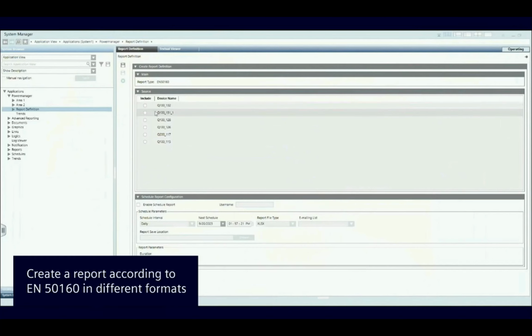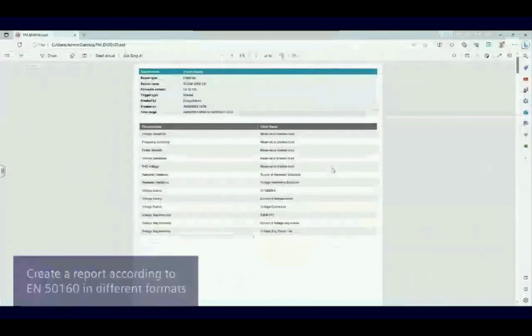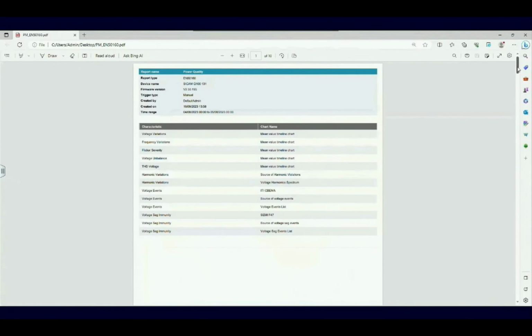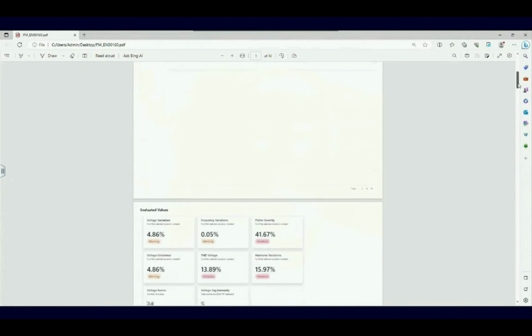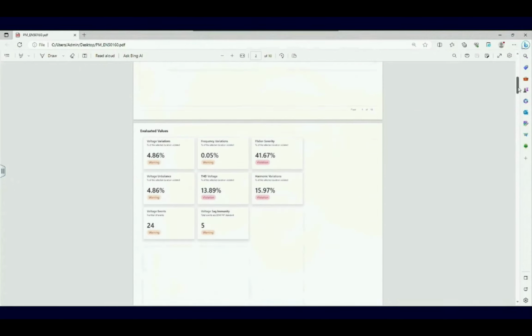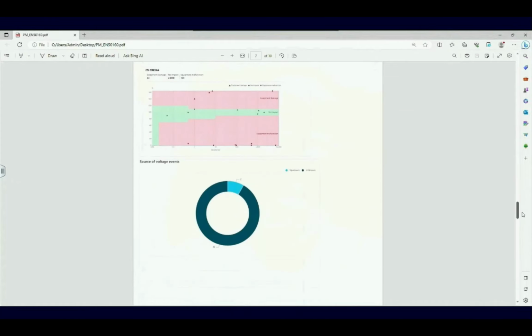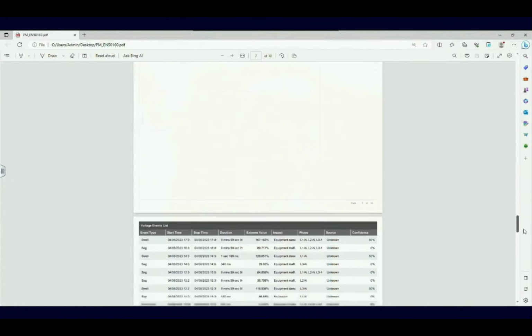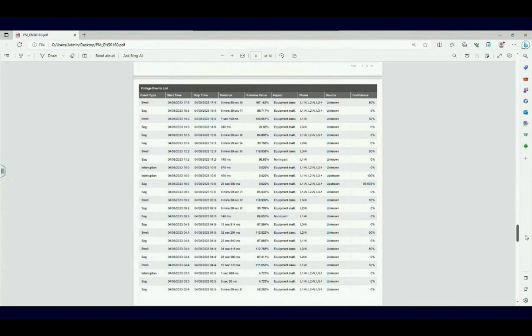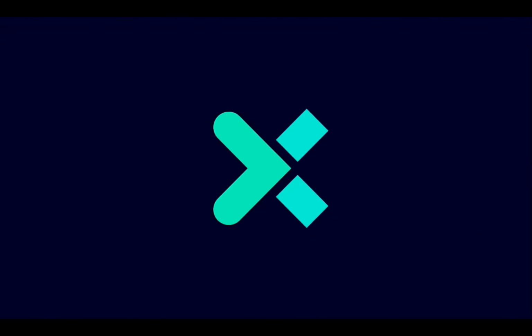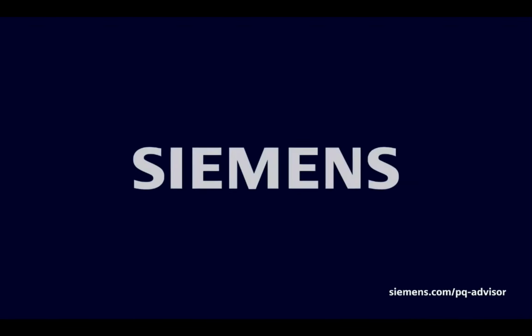Now going back into the standard client, you would define a report, select all the measurement points, and get an automatic report according to the EN50160 standard, which can be sent via email or stored in a location automatically. This gives you continuous reporting to visualize all your power quality data, store it, and have it archived, so you can see over time whether you had continuous improvement or everything is fine as it should be.